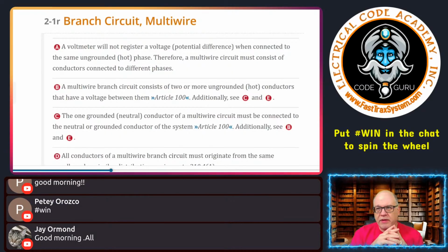Now, this can be used for a 240 volt circuit where you're using the black and the red. So it's single phase, so line 1 to line 2, or leg A to leg B. That could be used as a 240 volt circuit. And since it has a neutral, if it's a 240 volt load that has a neutral load, then it can be used to handle any part of that, line 1 or line 2 to neutral, that may run some other component in a piece of equipment.